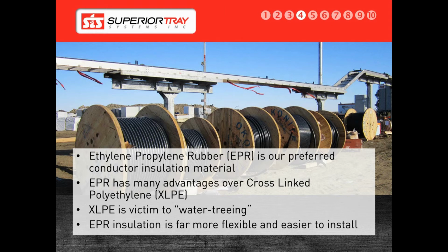The second issue with XLPE insulation is their resistance to cold temperatures. At low temperatures, an XLPE jacket will become brittle and can crack if stressed. XLPE is not meant for low temperature environments. EPR retains its flexibility at very low temperatures so that there are no detrimental effects on the conductor. This is relevant if a system is being installed in an area that can see ambient temperatures of -30 to -40 degrees Celsius or -22 to -40 degrees Fahrenheit.